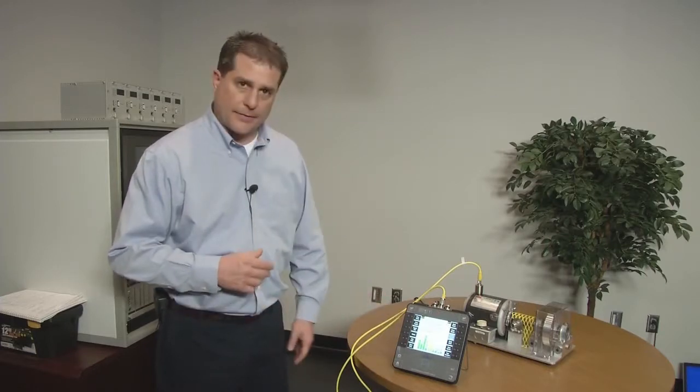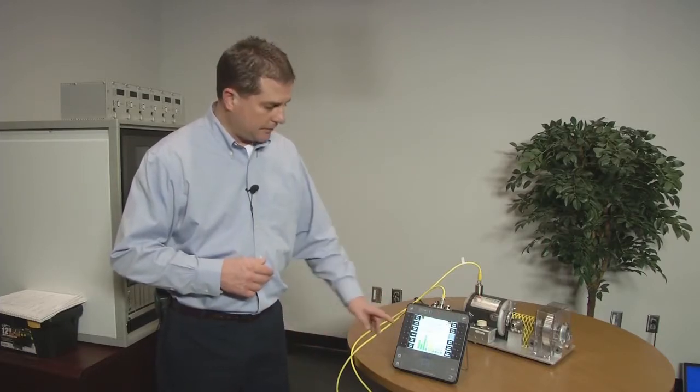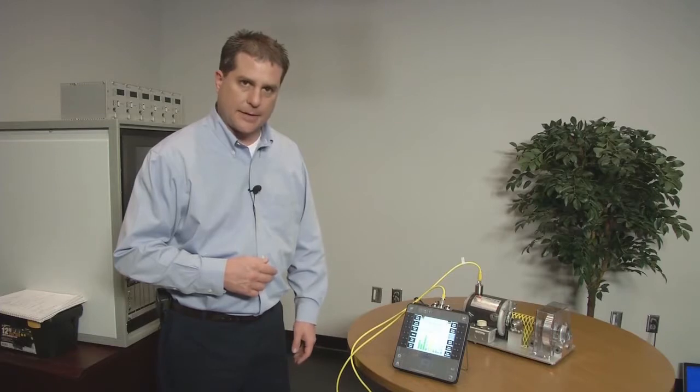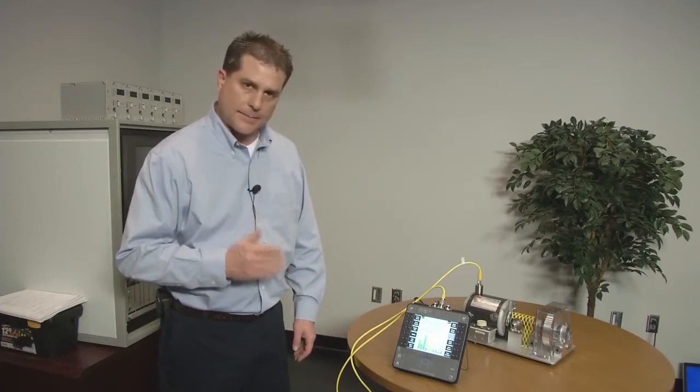So let's say you're out in the field, you collect some route vibration, and you see some alarms on the screen like I've got here. I've got high one times, high two times.